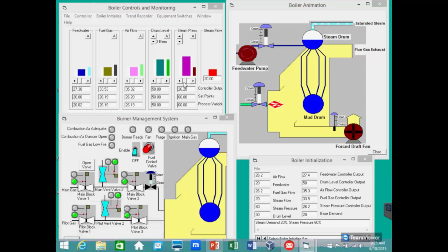And this is actually a live system, where you can see the feed pump running and the forced draft fan running. They have 7 different exercises that they do so they can see how fuel flow works versus airflow, how drum level works versus feed water flow, and also what concerns you have about implosion in the boiler and how to protect against it. All this is a live setup, a way of reviewing what they've learned the first 2 days by me talking about individual components.